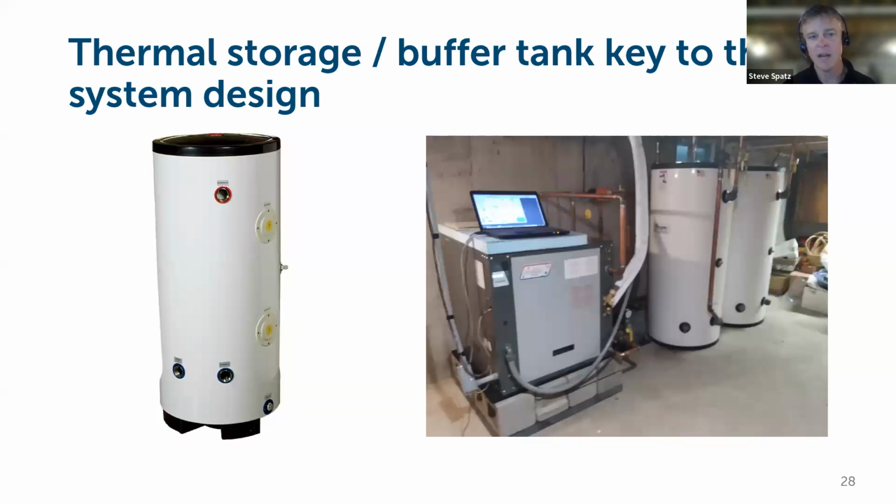The capacity of air to water heat pumps and their ability to generate capacity down in cold temperatures is more than enough, really, in most any system design to be the sole source of BTUs for that thermal storage tank throughout the heating season. Remember that 99% design temperature I was talking about at the very beginning. So 99% of the year, -11 or above is what the building will be seeing.